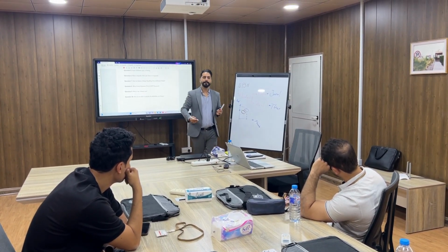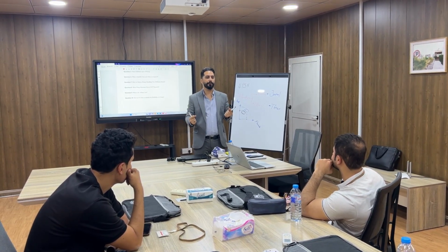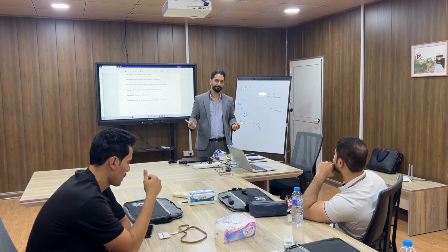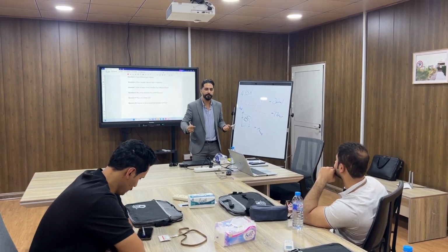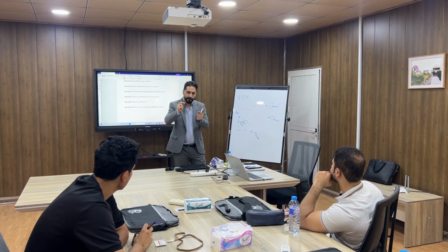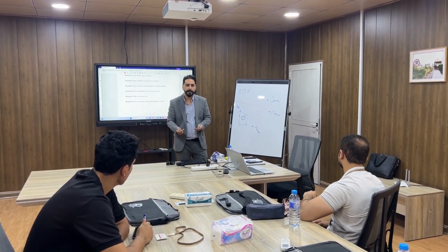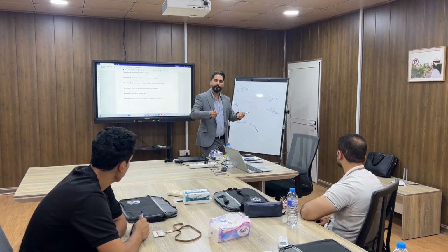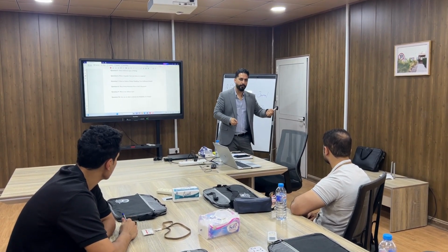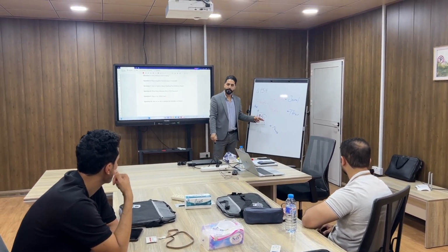A very common method of changing the head and flow rate which is produced by the same pump is called impeller trim. And impeller trim is actually decreasing the length of the impeller, and we are going to talk about it. The other common method is to change the opening of the discharge valve. Okay? By pinching or by closing the valve or opening the valve, we can change the flow rate.